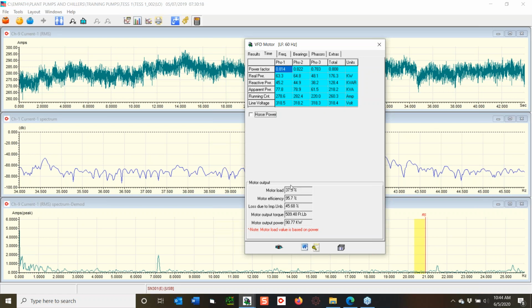So here's my nameplate. It's saying we're at 38% load. It's got a pretty good efficiency. Losses due to impedance unbalance. That's the loose connection, so I've got significant losses across that unbalance. I can look at this as horsepower instead. But across here, I'm expecting the power factor to be relatively low because it's on the output of a VFD. That's actually pretty darn good.